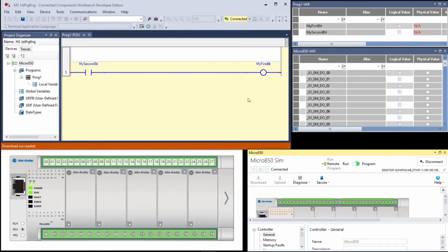We have this downloaded, and in your manual, it told you to take note of the color of the rung lines compared to the earlier color in the run mode. Well, earlier this was all red, right? But notice there's still a little red right there at the beginning of the rung. That is because this power bar, if you want to call it that, gives every rung a rung-in true state. At this point, the rung is true right here.